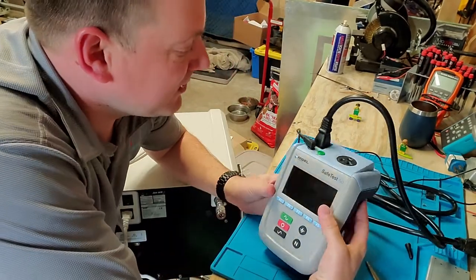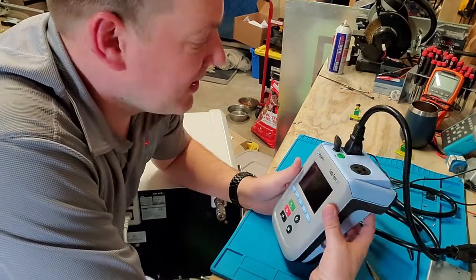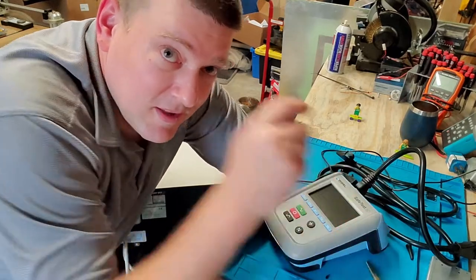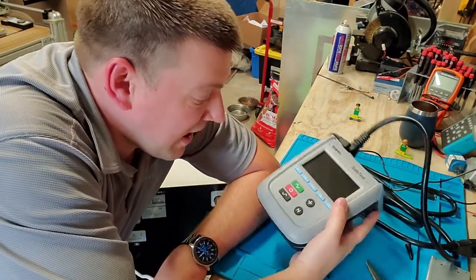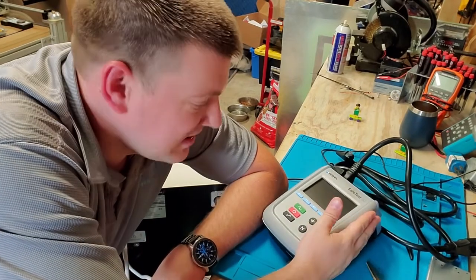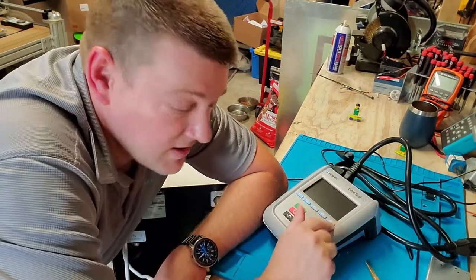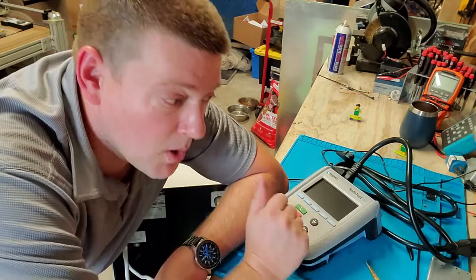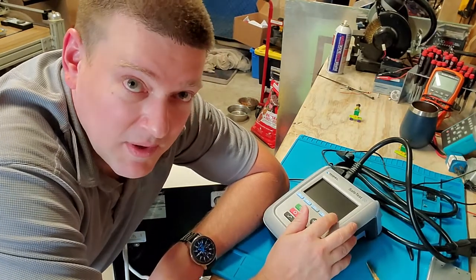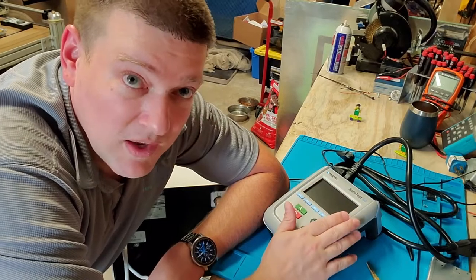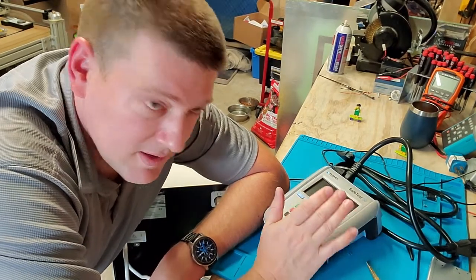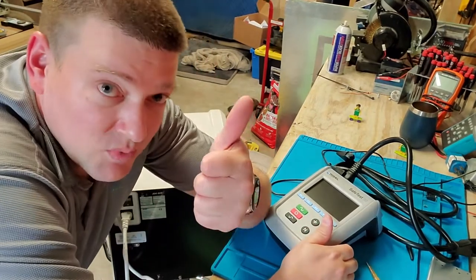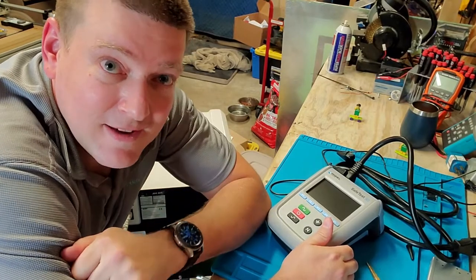It's the Rigel SafeTest 50. Guys, I absolutely love this. Thank you guys for sending this to me, the guys out there at Argo Biomedical. Again, the link's going to be in the description below, and I'm going to be doing lots of videos with this guy here at my side, because not only can we use it for electrical safety, but like I said, we can use it to test the equipment draw current. So if I've got a motor that's going bad, let's say I've got a heating element that's not quite working well, there's a lot of things that we can do to figure out what's going on with the device using this one here, because it's got manual menus. I really dig that. Anyway, thanks Rigel, thanks Argo Biomedical, and thank you guys for watching.